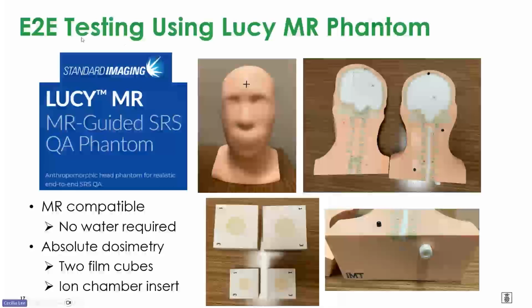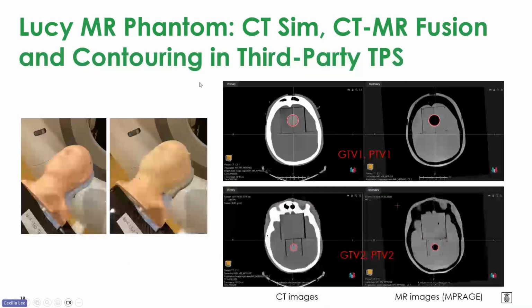Using that workflow, we performed the end-to-end testing using the standard imaging LUCY MR phantom. This phantom is MR compatible. A lot of phantoms you have to add water to, but this one doesn't require water, which is pretty convenient. It has 2 film cubes, a larger one and a smaller one, so you can insert film and then irradiate it. And there is an ion chamber insert, so you can insert an ion chamber and measure absolute dosimetry.